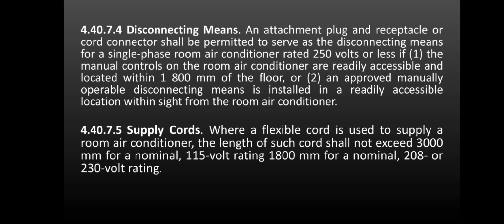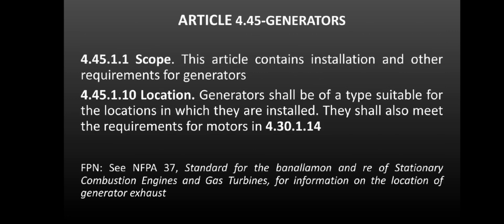Supply cords. Where a flexible cord is used to supply a room air conditioner, the length of such cord shall not exceed 3000 mm for a nominal 115 volt rating and 1800 mm for a nominal 208 or 230 volt rating.